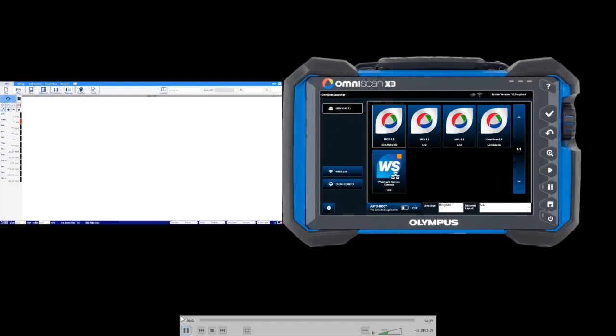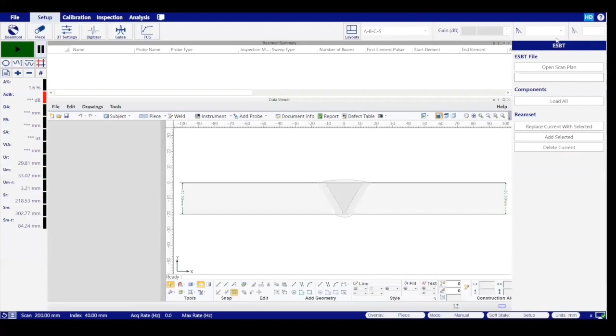We have a WeldSight Remote Connect app, which acts as a bridge between WeldSight and our X3. We just use an Ethernet cable to configure the IP addresses of the equipment, and the launch configuration tool on WeldSight is used to detect and troubleshoot any errors in settings. As you can see here, my X3 is directly detected, and I'm able to configure the IP addresses. Once it's connected, the X3 can be used as a black box, and all the controls can be taken over from WeldSight. Starting with the scan plan.